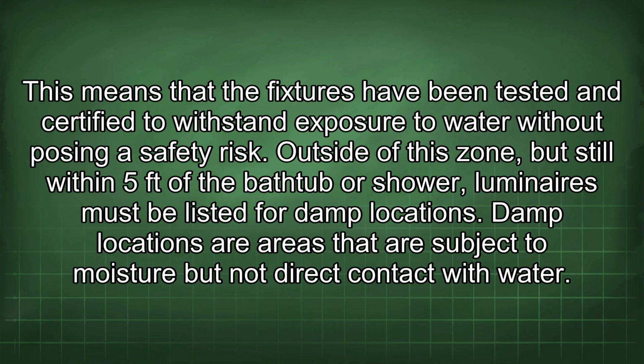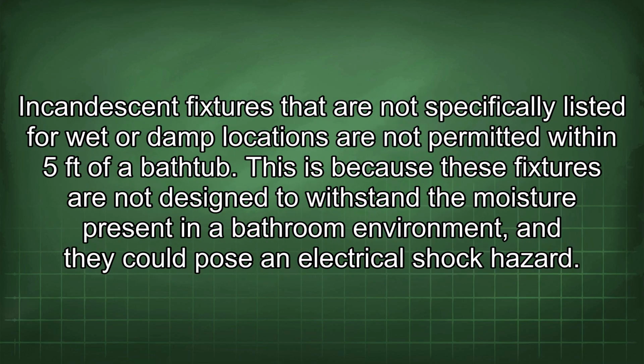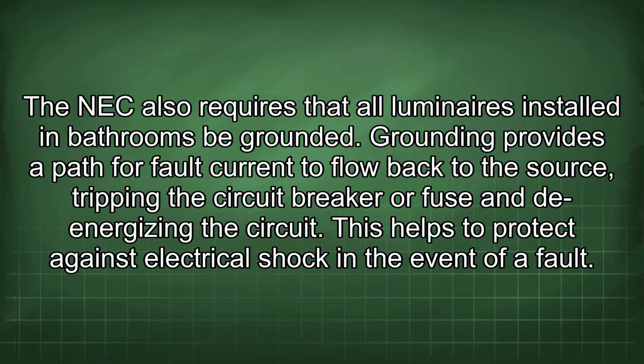Outside of this zone, but still within 5 ft of the bathtub or shower, luminaires must be listed for damp locations. Damp locations are areas that are subject to moisture but not direct contact with water. Incandescent fixtures that are not specifically listed for wet or damp locations are not permitted within 5 ft of a bathtub. This is because these fixtures are not designed to withstand the moisture present in a bathroom environment, and they could pose an electrical shock hazard. The NEC also requires that all luminaires installed in bathrooms be grounded. Grounding provides a path for fault current to flow back to the source, tripping the circuit breaker or fuse and de-energizing the circuit. This helps to protect against electrical shock in the event of a fault.